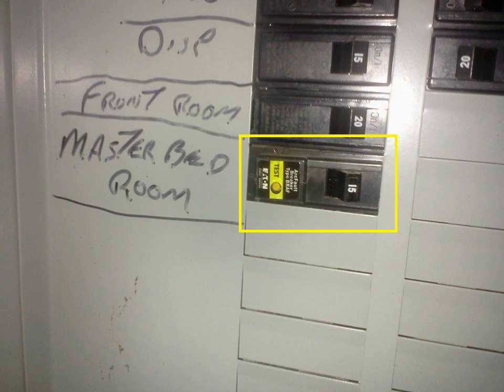In the UK, the 2018 edition of the Wiring Regulations is the first edition to make any mention of arc fault devices, indicating they may be installed if the design has an unusually high risk of fire from arc faults. The annexes relating to testing indicate that when AFDDs are installed, their correct operation must be verified before completion, but the method of testing is not described. This is in contrast to RCDs, where a number of trip times at different fault current levels must be verified.